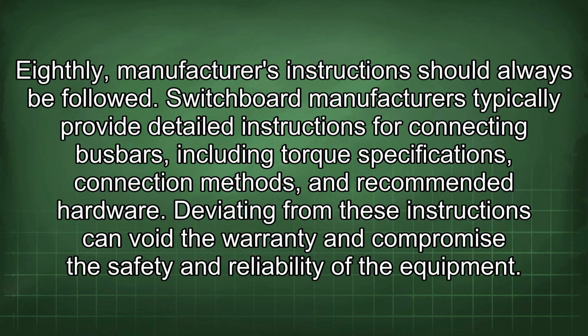Eighthly, manufacturer's instructions should always be followed. Switchboard manufacturers typically provide detailed instructions for connecting busbars, including torque specifications, connection methods, and recommended hardware. Deviating from these instructions can void the warranty and compromise the safety and reliability of the equipment.